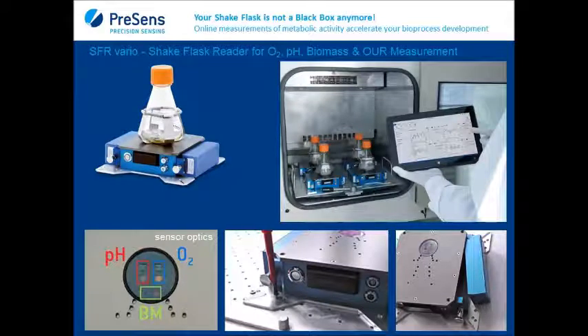Like I mentioned before, the device will fit in any commercially available shaker. You do not have to do any modifications to your existing equipment. And the software it comes with will operate 4 devices, like I mentioned before. Here on the bottom left of the page, you can see the actual optics. They consist of a light source and a detector for each parameter. And for the biomass measurement as well, you have a 560 nanometer light source and the scattered light detector.